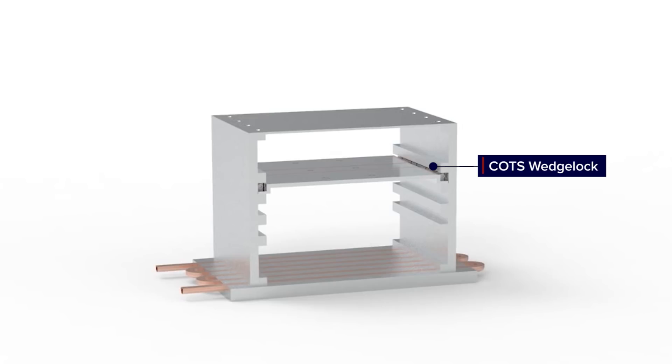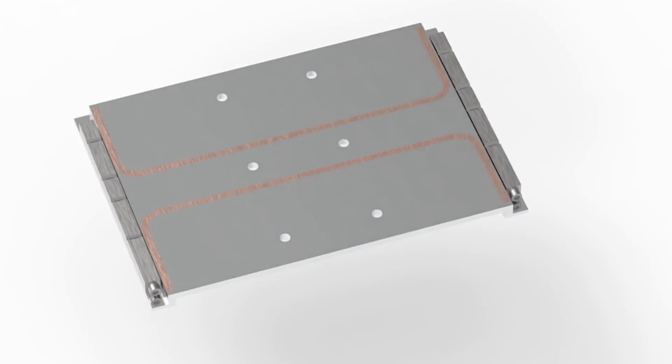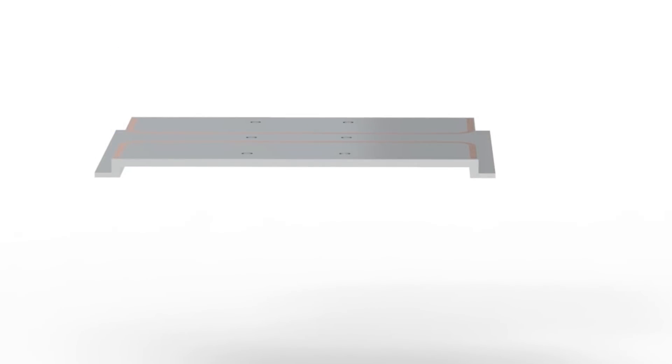The next area for thermal enhancement is at the frame-to-chassis interface. Off-the-shelf wedge locks provide mechanical attachment, but are not efficient heat transfer devices. Due to limited surface area and poor thermal path through metal-to-metal interfaces, the overall delta T is pretty significant for a short conduction path.